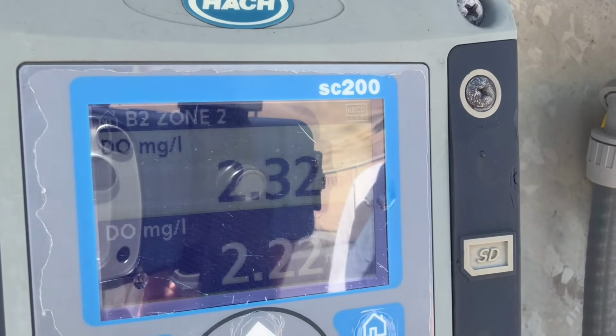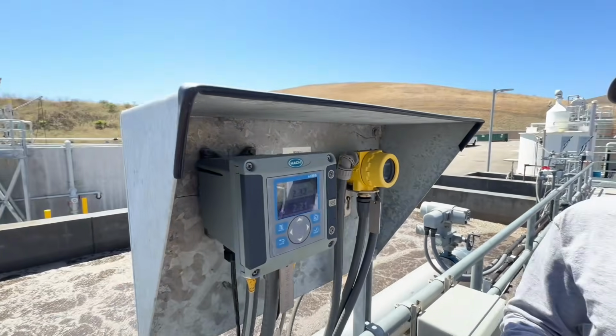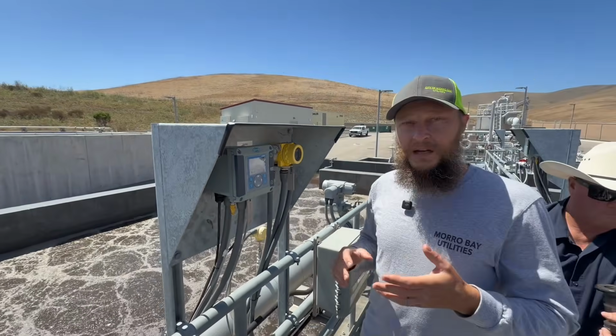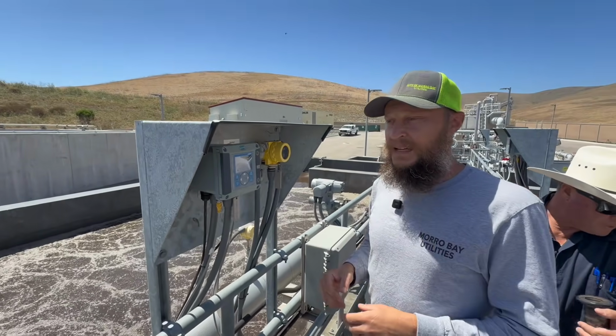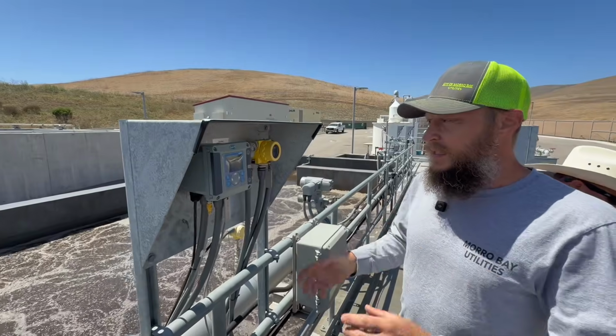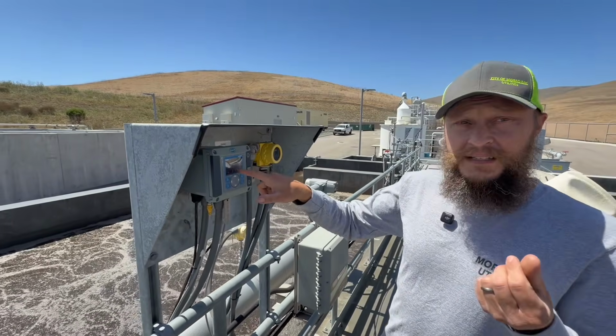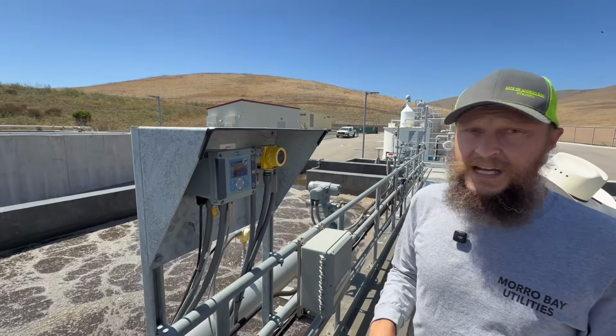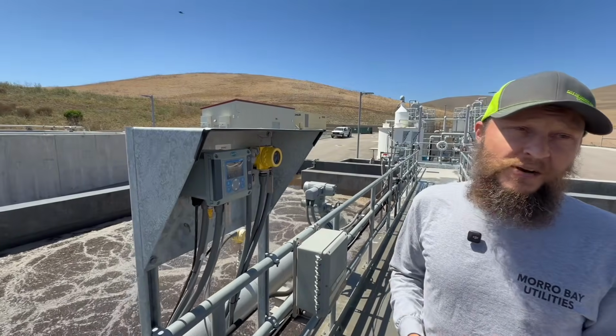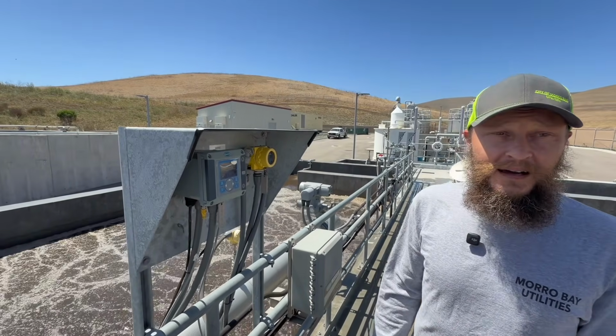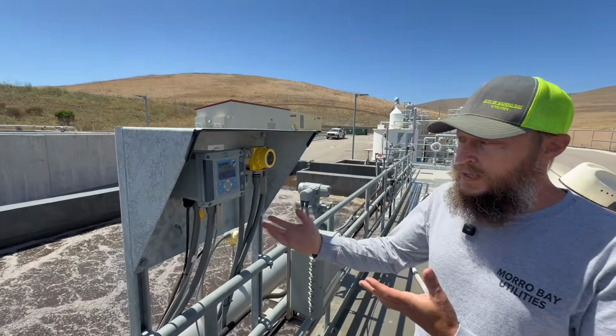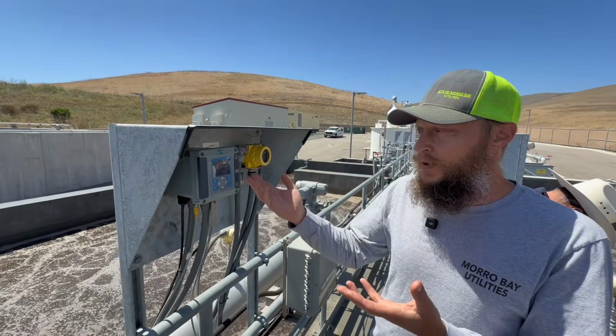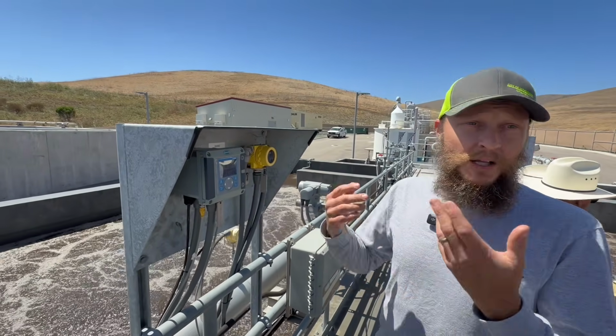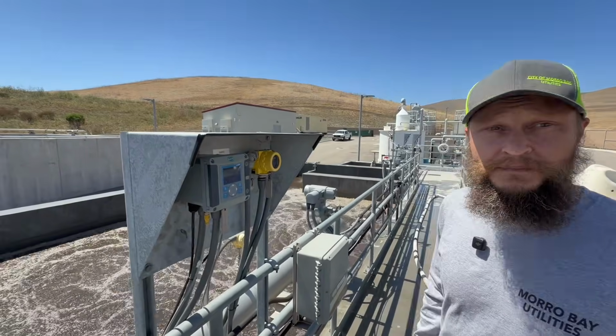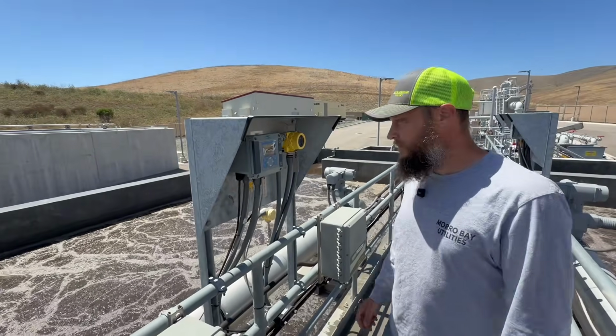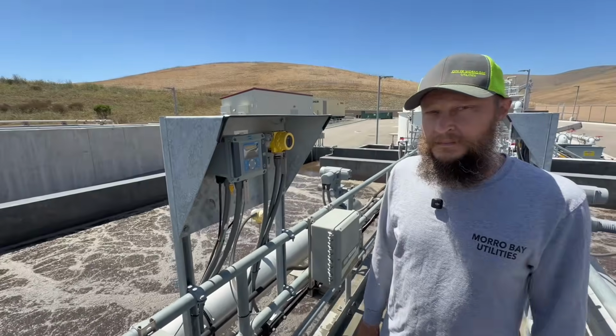So that number right there is being pushed over to the PLC that we were just at via a 4 to 20 signal. And then the SCADA system is scaling that current that's flowing through the wire back to that 2.3. And then we historize it. We can view it on the HMI. We can also take it in and out of service, because that number is related to high and low DO alarms as well. Excellent. So Grant, you mentioned a 4 to 20 milliamp signal. What exactly does that mean?